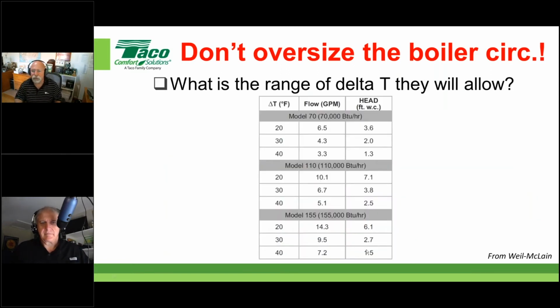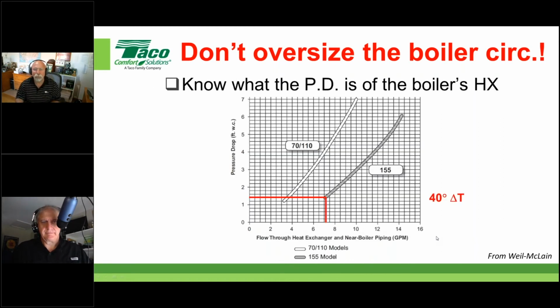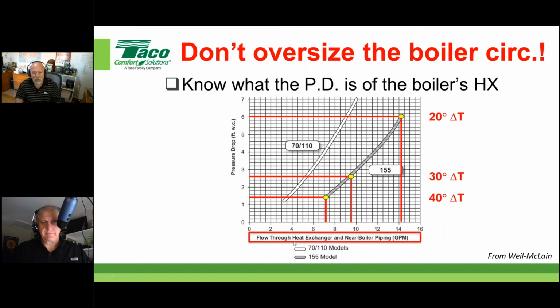Let's do one more. Here's one from our friends at Weil-McLain, on their 155. There's a 20, a 30, a 40. See where this is going. Here's what their chart looks like. I will bring up one point about the way this is done. It's similar, but at the bottom here, I want you to understand they've added into their pressure drop some near-boiler piping, so there's an additional number there. You can do a comparison and just figure it out.